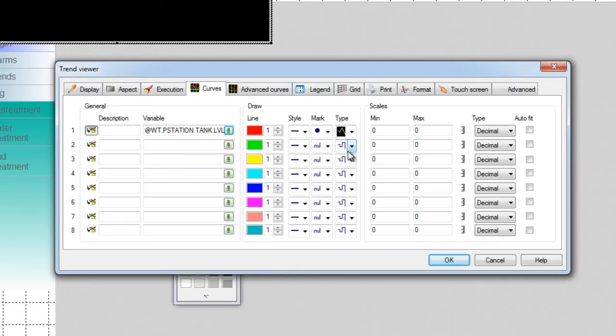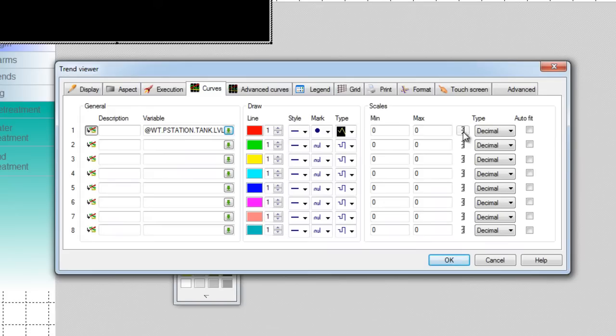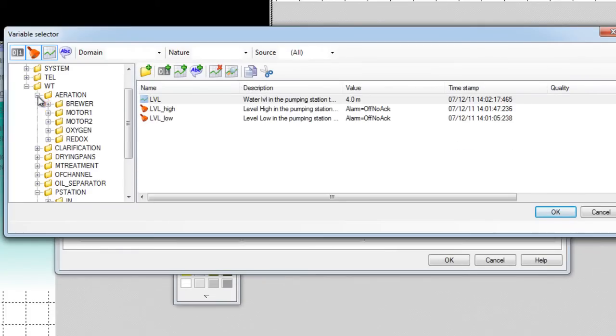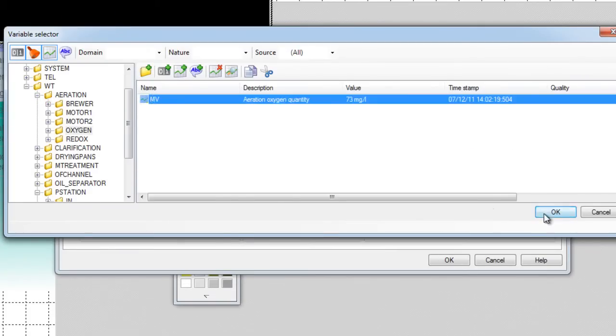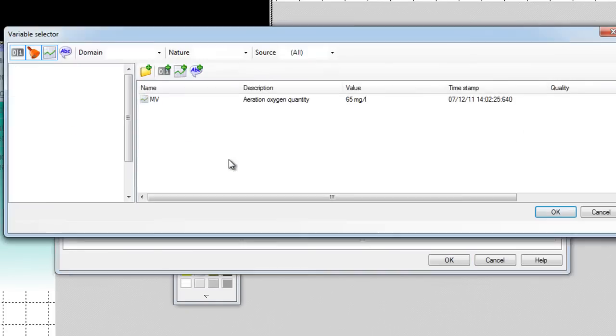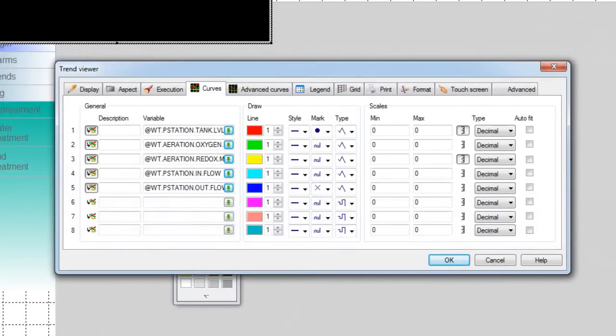You can change here the min-max range of the variable within the trace. And by default, the variable's properties at runtime are used. It's also possible to display a scale for the trend. It's important to note that it's also possible to change these parameters in runtime, either from a SCADA Basic program or from the legend. We define now several other variables to be displayed. And that's it!